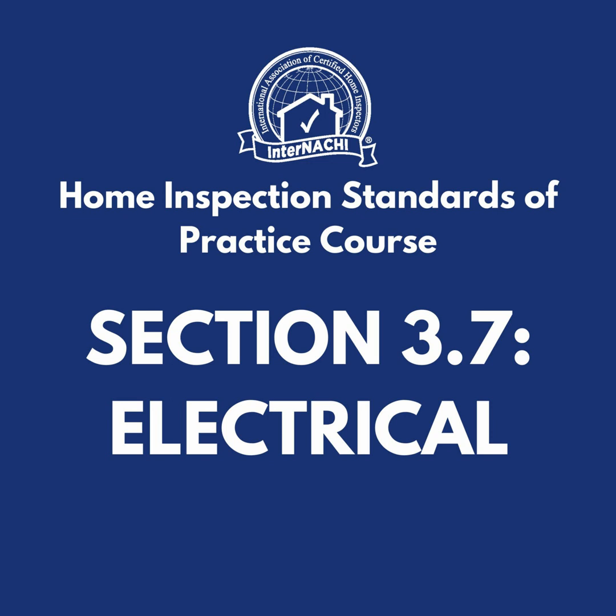Service. Service is a term used to describe the conductors and equipment for delivering electricity from the utility company to the wiring system of the building served. Only one is typically installed for a dwelling. A minimum of 100 amp service is needed for a single residence. The service entrance cable, SEC, is a line of service conductors located between the terminals of the service equipment, or main disconnect, and a point usually outside the building, clear of building walls, where they are joined by a tap or splice to the service drop or overhead service conductors.